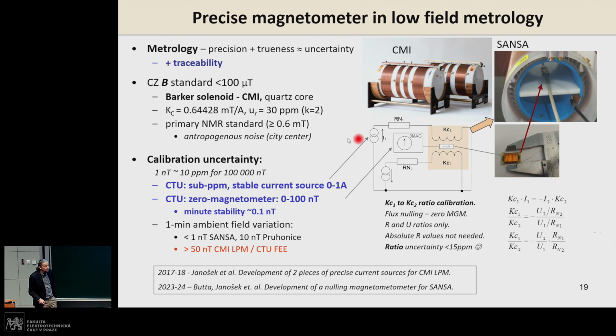And because metrology is focused mainly on traceability, I am showing here that the flux density standard for the Czech Republic is actually a solenoid on a quartz core. Even though it's calibrated against the primary standard at the Metrology Institute working on nuclear magnetic resonance, the anthropogenic noise at the Czech Metrology Institute is very high, and it doesn't allow us to go with the calibration uncertainty to the original values achieved in the 1980s. So this number actually got worse by 1 order of magnitude.